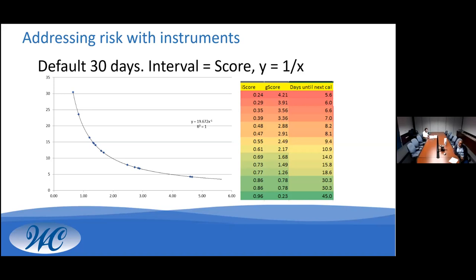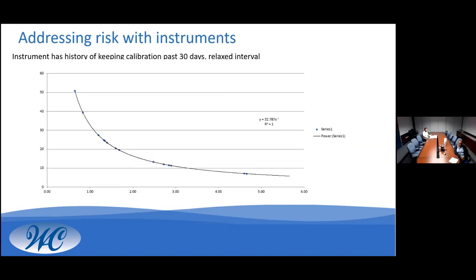If you can see in front of the X, there's a number, pay attention to that because that introduces a dynamic element to our function. This graph shows an instrument that has a history of keeping calibration past 30 days. Calibration scores are calculated and used to determine the interval with a default max of 30 days, as I mentioned. The dynamic aspect of our calibration algorithm takes effect when individual instrument risk values are incorporated into our calculations.